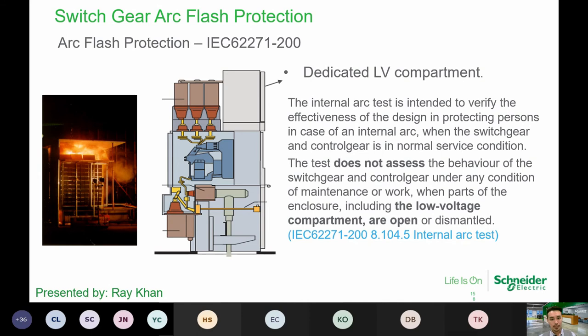All right, but this test is done when the panel is closed. So what we are trying to say is that if you were to open this door when the panel is live, we are exposing the person to risk. Even if he's accessing the low voltage compartment, if the model doesn't have a double door, then that will put him in a lot of danger. Right, so that is why Schneider Electric came up with a dedicated low voltage compartment, to eliminate the possibility of such danger itself.